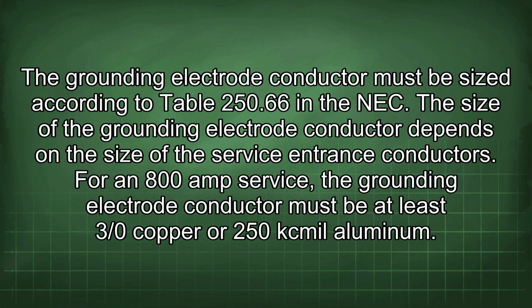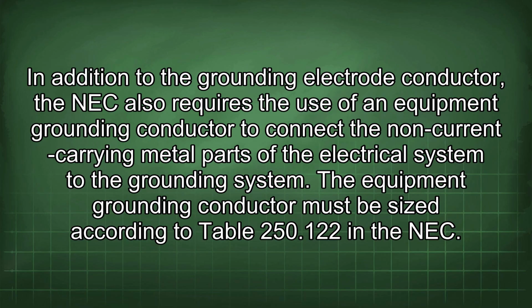The grounding electrode conductor must be sized according to Table 250.66 in the NEC. The size of the grounding electrode conductor depends on the size of the service entrance conductors. For an 800 amp service, the grounding electrode conductor must be at least 3/0 copper or 250 kcmil aluminum. In addition to the grounding electrode conductor, the NEC also requires the use of an equipment grounding conductor to connect the non-current carrying metal parts of the electrical system to the grounding system.